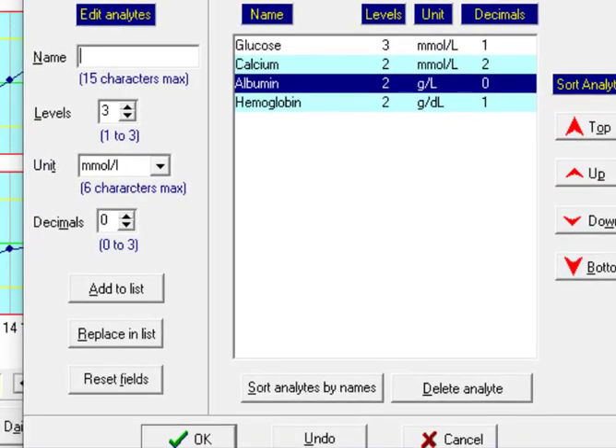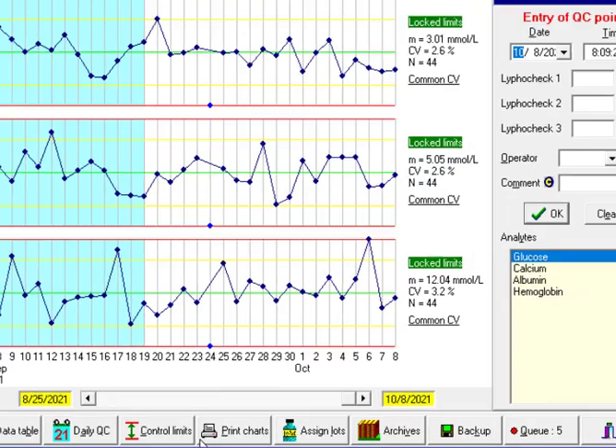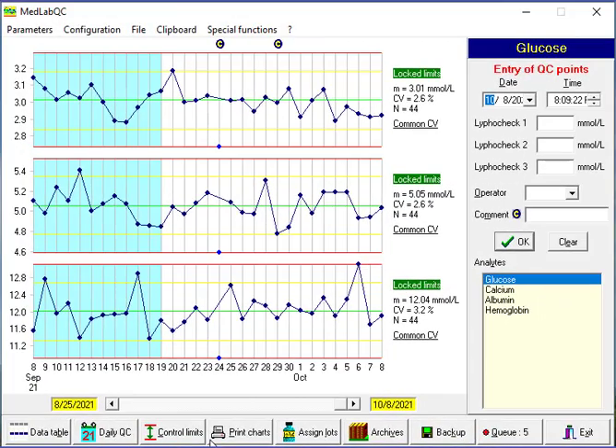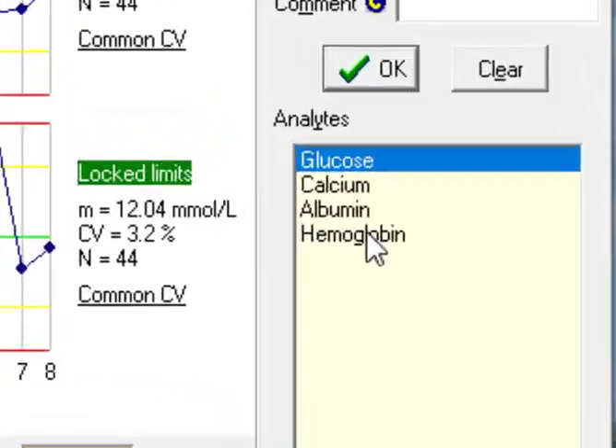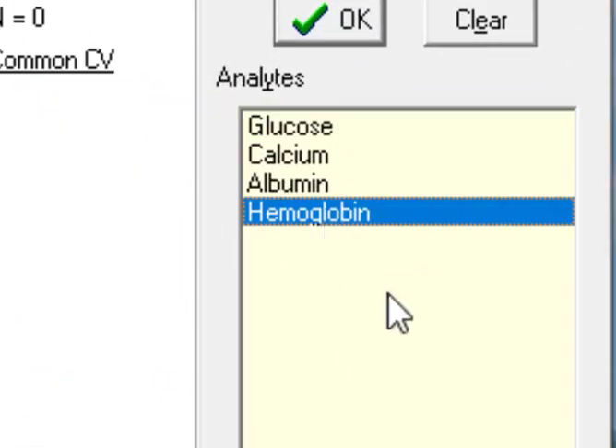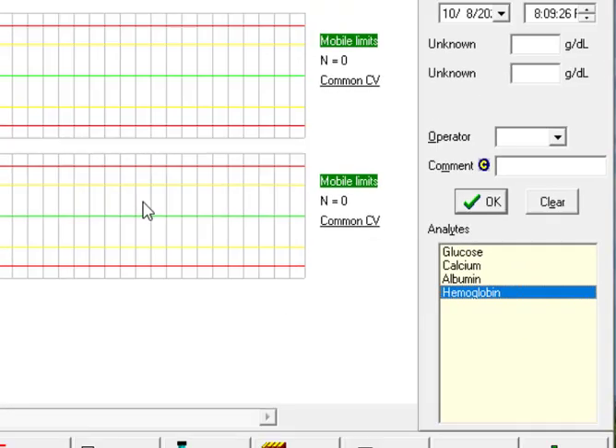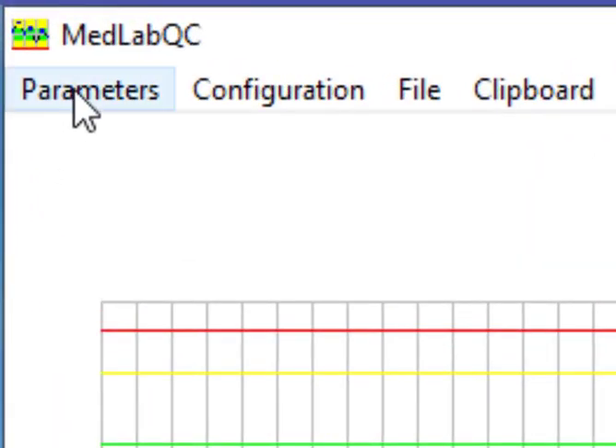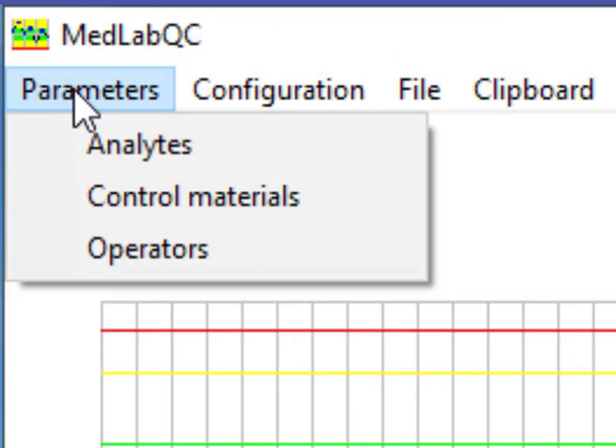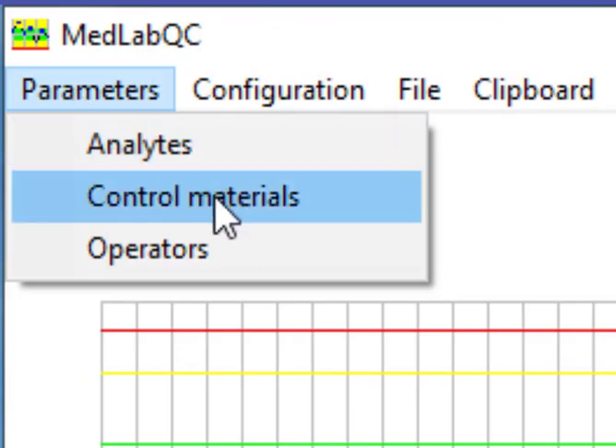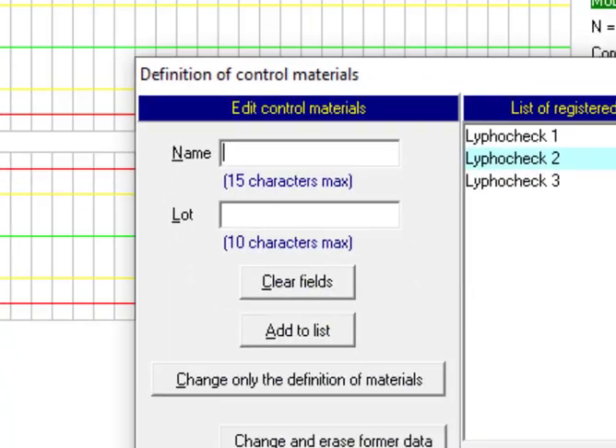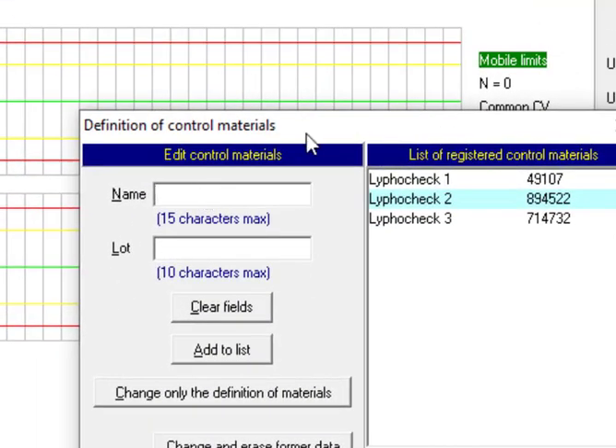Before leaving the window we have to press OK in order to be saved. And now we have hemoglobin on the right side of the screen. So we have to define control material for this analyte. These are control materials that has been defined before.